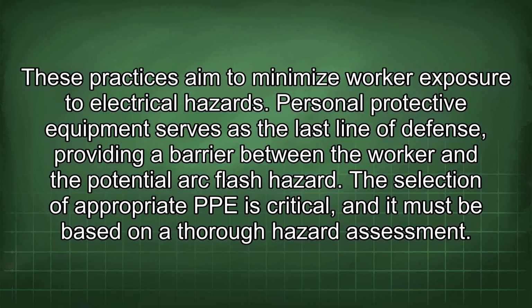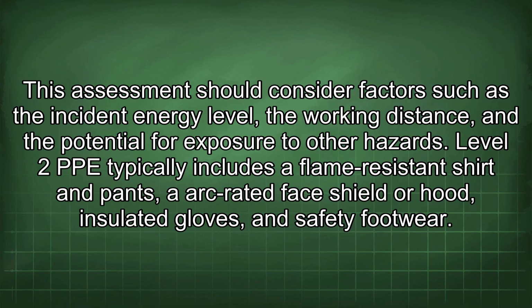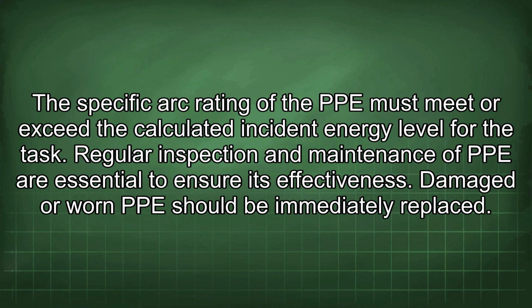The selection of appropriate PPE is critical, and it must be based on a thorough hazard assessment. This assessment should consider factors such as the incident energy level, the working distance, and the potential for exposure to other hazards. Level 2 PPE typically includes a flame-resistant shirt and pants, arc-rated face shield or hood, insulated gloves, and safety footwear. The specific arc rating of the PPE must meet or exceed the calculated incident energy level for the task. Regular inspection and maintenance of PPE are essential to ensure its effectiveness. Damaged or worn PPE should be immediately replaced.